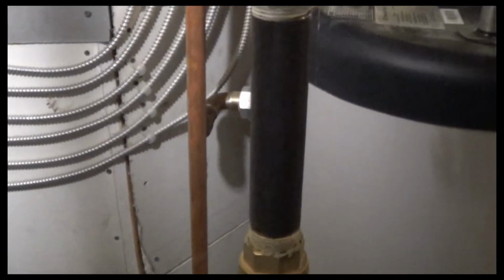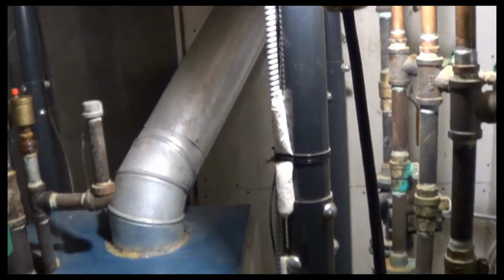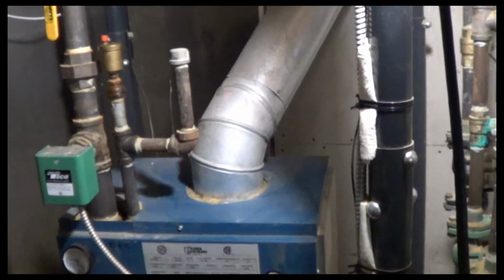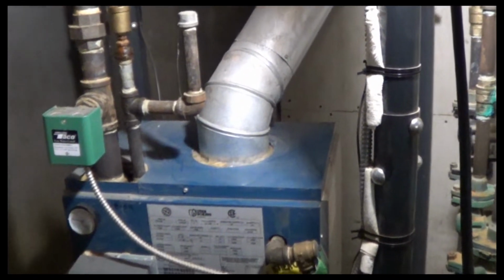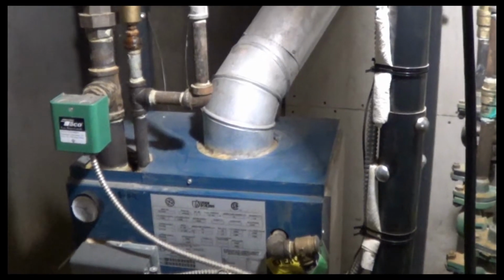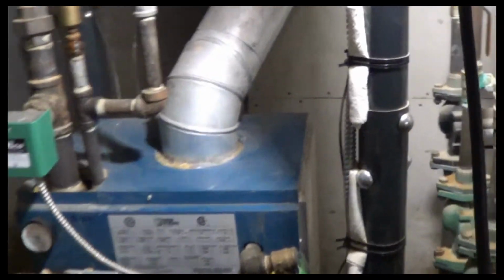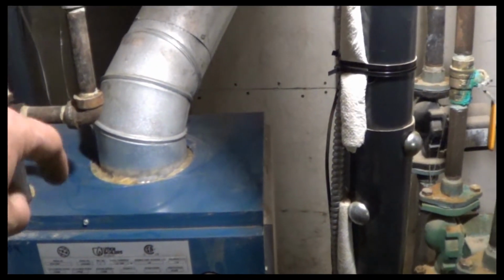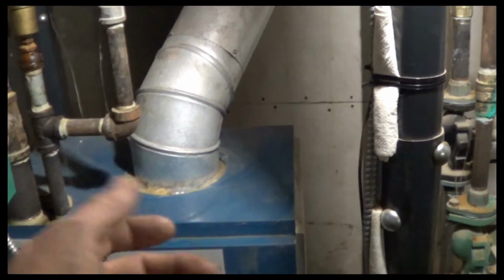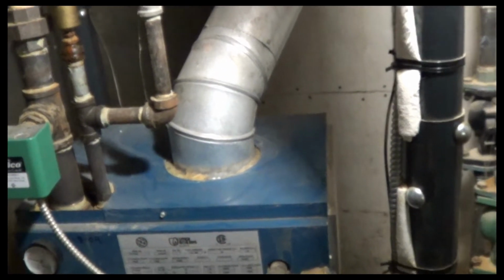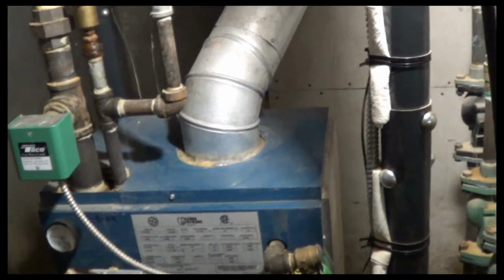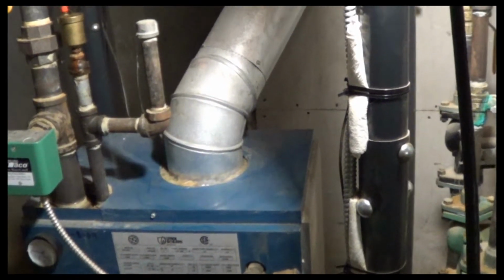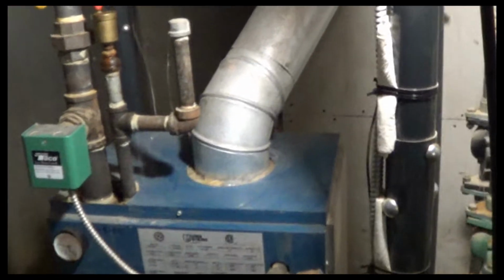Alright, let me pause this and get going on the clean and check. I'm going to start by taking the smoke pipe down. I already did a pre-check on the efficiency and CO, combustion analysis. I'm going to take the top off - this top right here, that smoke pipe's coming off. I'm going to pull that out, you'll see me take it apart, and go down through there with a brush and a soot vacuum to clean it out. I'll take a shot of it when I get it off. I'll be back with you, see you soon.